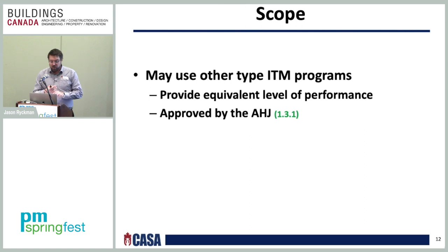Also, with the NFPA 25 document, when you're using it, you can use a different type of ITM program. But if you do so, you have to provide an equivalent level of performance that has to be approved by the authority having jurisdiction, which is usually the fire service. So if you choose to go outside the box of NFPA 25, you can create your own ITM program, but it has to be an equivalent level of performance and approved by the authority having jurisdiction.